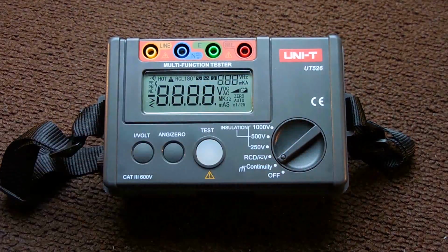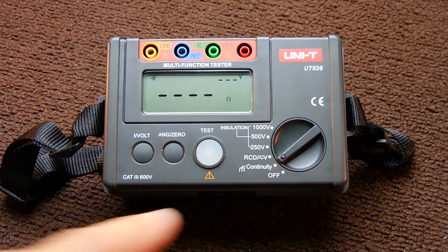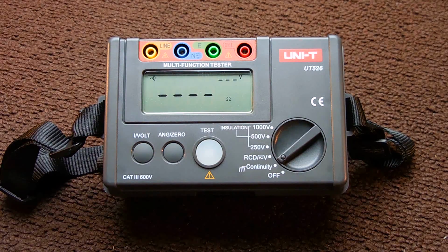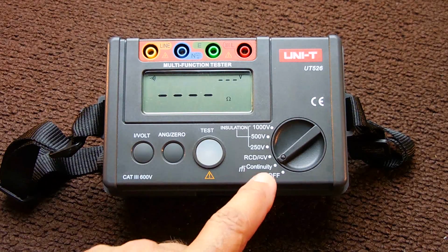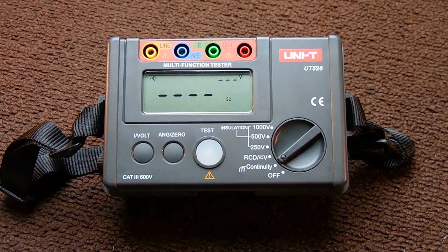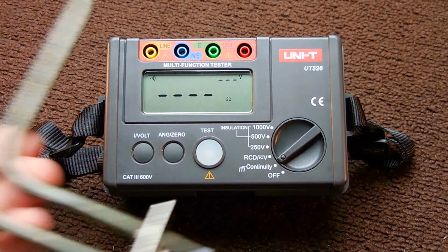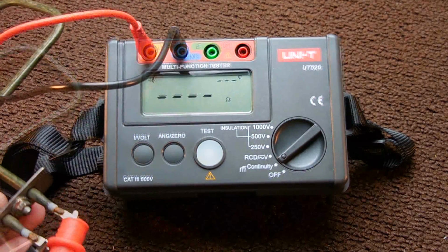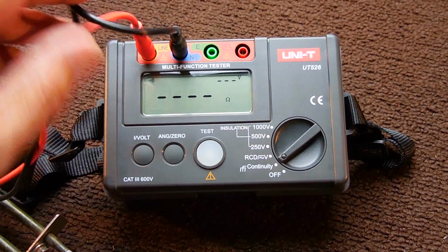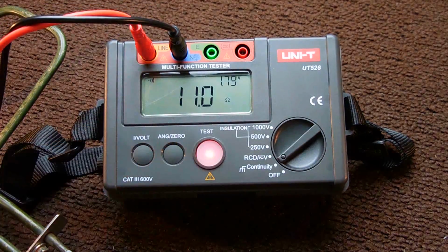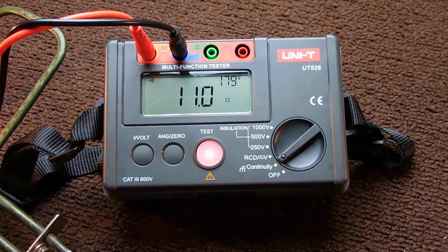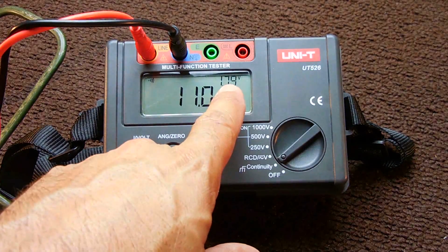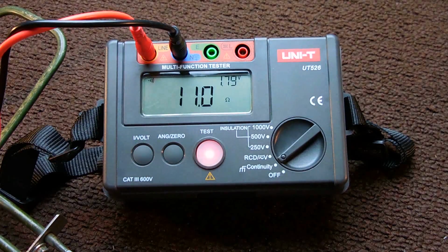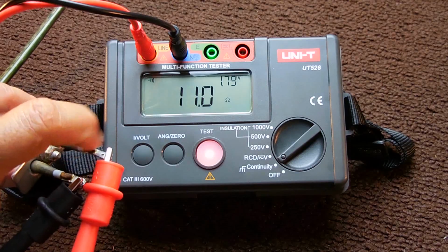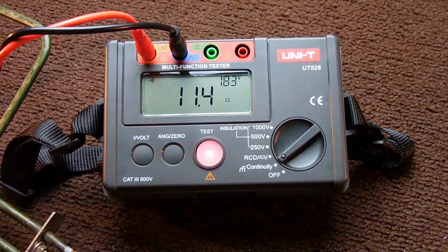First, let's turn it on. On this setting right here, you'd be checking protective earth conductors for ground purposes. So this goes from 0 ohms all the way up to 2 kilo ohm. So if I wanted, I could easily check the resistance across this heating element. I'll show you that quickly. Once that's connected, you're going to push the test button, and you can see it's 11 ohms, this heating element, and the voltage during the test right now is at 1.79. So it's 1.79 volts measured across these terminals, and we have around 11.4 ohms.